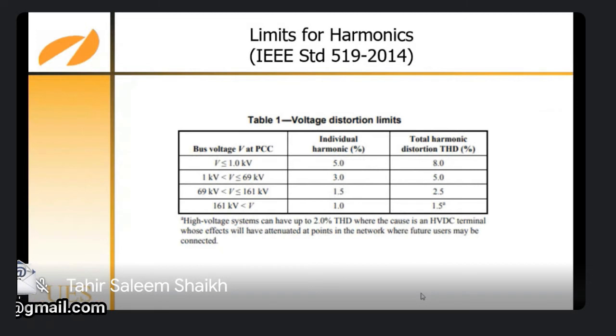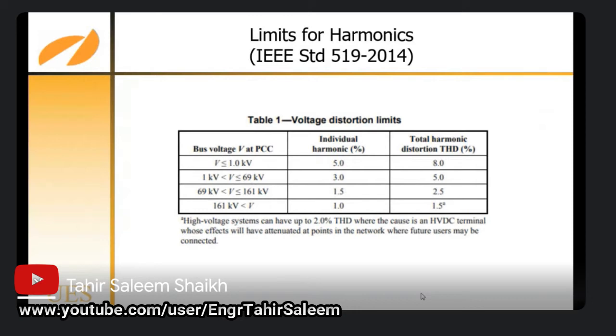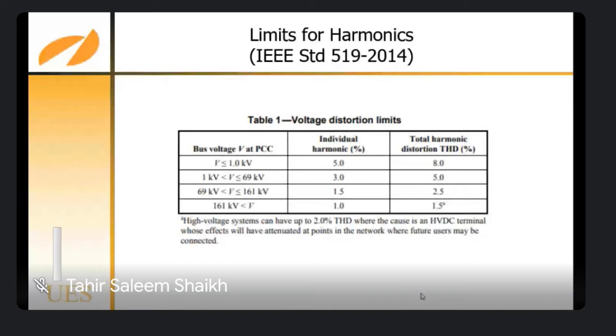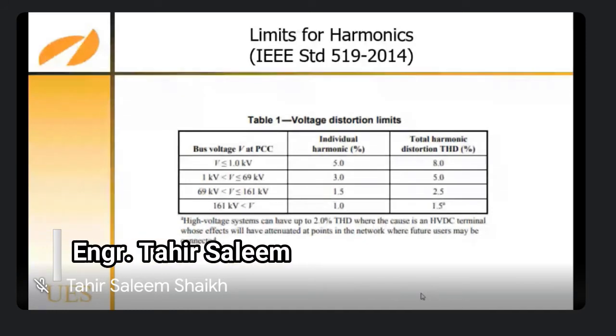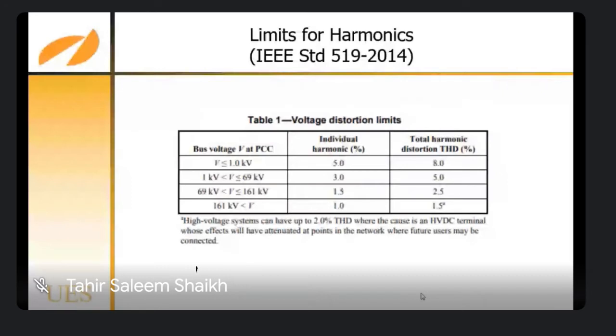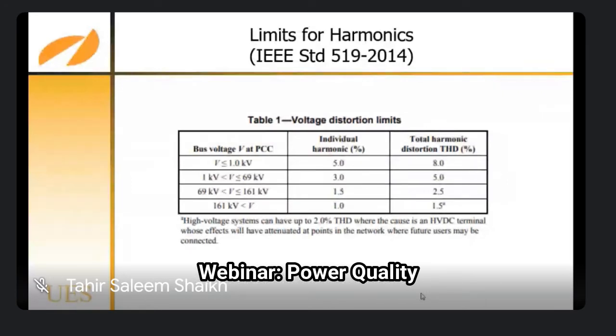Now, this is a standard. Another standard example. If your voltage is less than or equal to 1 kV, individual harmonics should be, in a generalized way, the harmonic limitation should be 5%, and total harmonic distortion, which is called THD, is 8%. I will give you the IEC standard also, which to some extent is similar. So 1 kV to 69 kV it is 3% to 5%. 69 kV to 161 kV is 1.5 to 2.5%. 161 kV or more voltage it is 1 to 1.5%. These are the standards specified in the standards books.